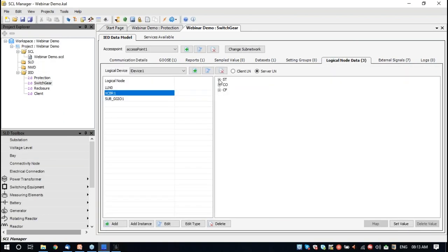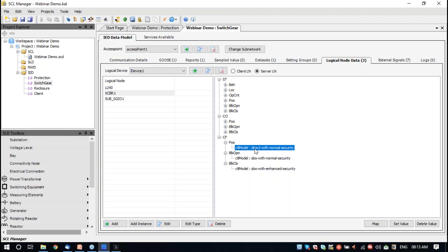Browsing to the report, there are two reports configured and both reports will be subscribed by the client. Browsing to the switchgear functionality, we have similar communication addressing and circuit breaker functionality. For the control purpose, we have a few data points which will explain the control functionality, so that we can simulate control function during this demo. We also have control models set to different parameters. We will mostly be performing control on the circuit breaker position. Direct with normal security is the simplest form of control, and we shall use this during the demo.